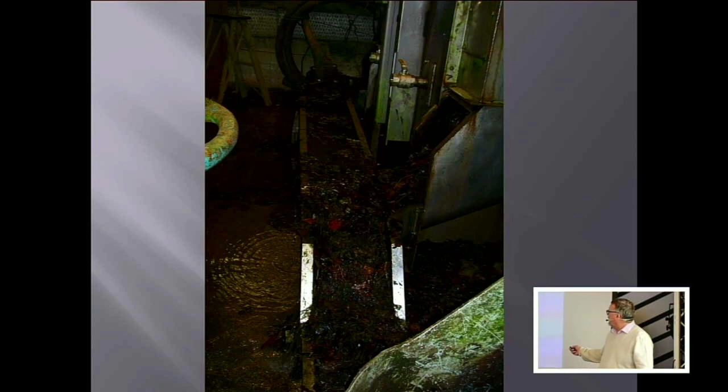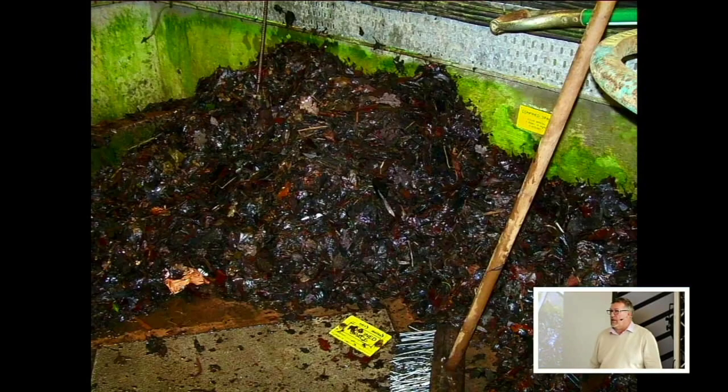Inside the intake itself, this is a stainless steel band screen with a giant sieve going round and round constantly. As the river goes round, you can speed these band screens up. The more leaves, the faster you can go. You can put two on, so there's two giant sieves going round, because the leaves themselves are a big problem.